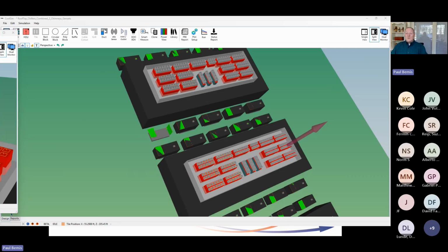The answer is, if you have an existing situation, both internal and external, right? If your data center exists and you can build a representative model, always validate it. Always go in and make some measurements and tune the model to match the results. I mean, CoolSim's been around since the 1980s. It's got a tremendous amount of validation on it. CFD can accurately represent physical phenomena to a high degree of accuracy, there's no question about this anymore. This is Fluent, this is running Fluent. The trick is making the measurement so that you can validate the model, because you have to make measurements.